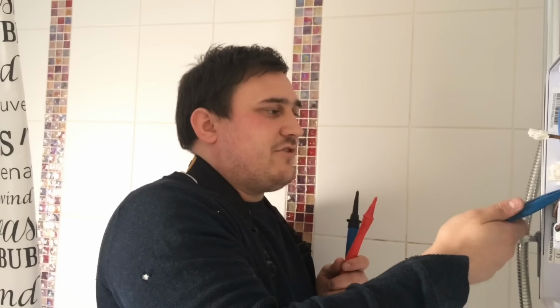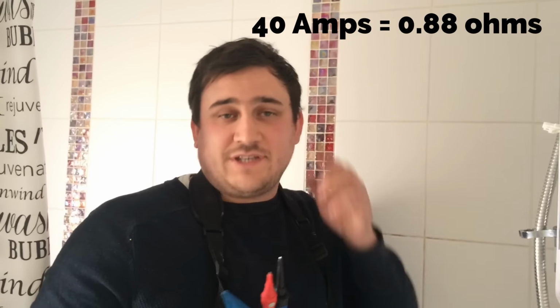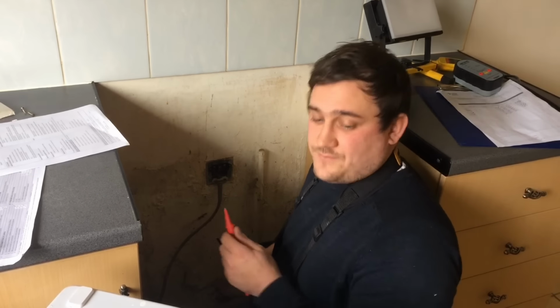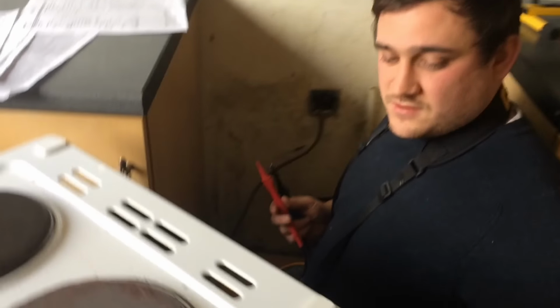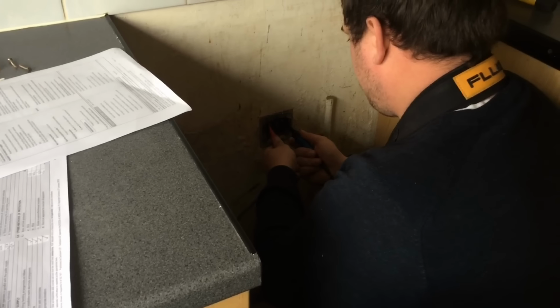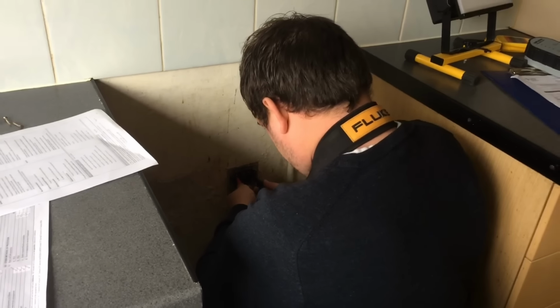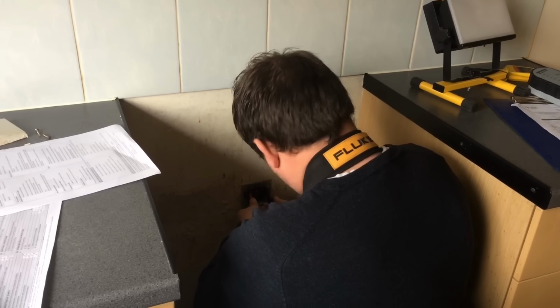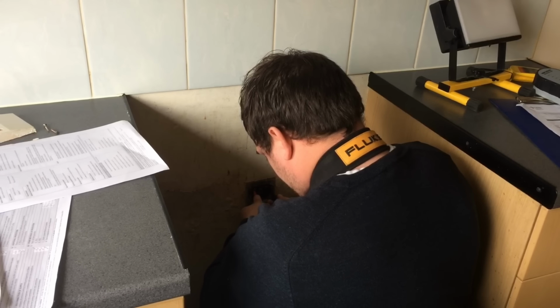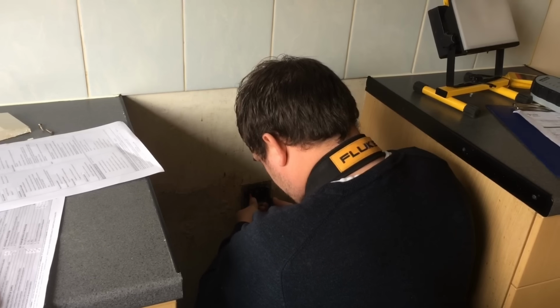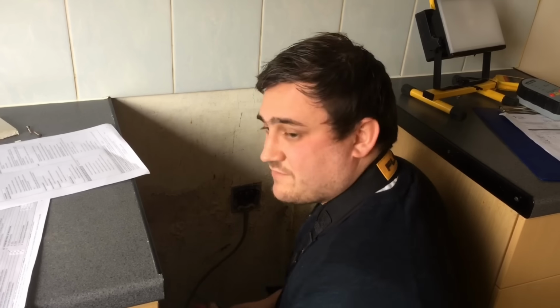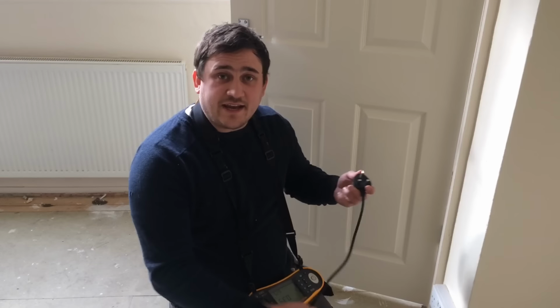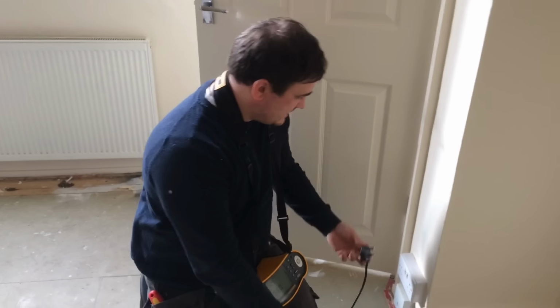We have a reading of 0.28 ohms. We will check that in our on-site guide for the maximum ZS values for a 40 amp breaker which the shower is on. We're repeating the same test now for our cooker circuit. So I've clamped onto the back of the cooker for our earth. So onto line and neutral. Oh, slipped off. 1.05 is our reading.